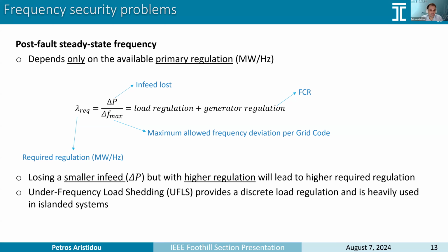Also, it should be noted that in most islanded systems there is also the under-frequency load shedding scheme, which provides discrete load regulation. So again, it's some megawatt per hertz, but in a stepwise manner. And this is heavily used in islanded systems, especially, for example, in Cyprus. We are going to see later that without the under-frequency load shedding scheme, most of the operating scenarios that we have now in Cyprus would actually not be secure.